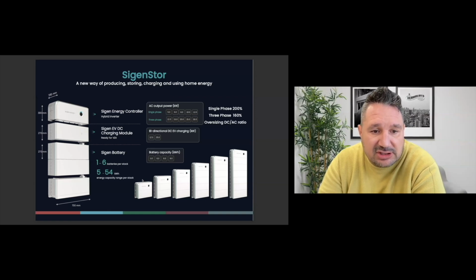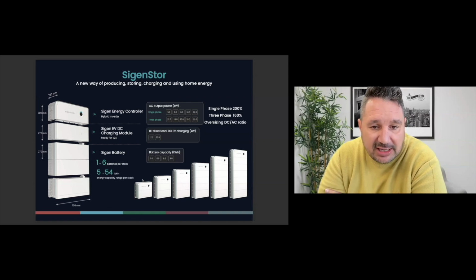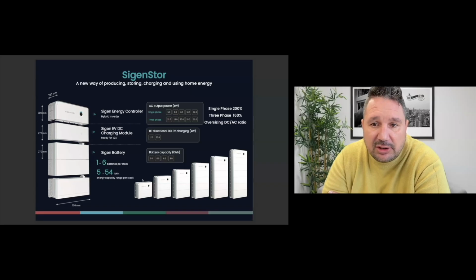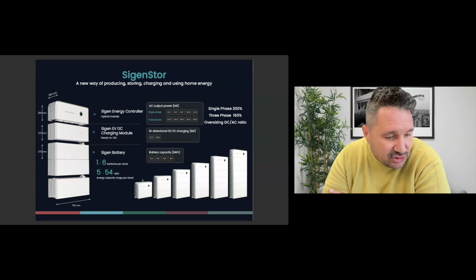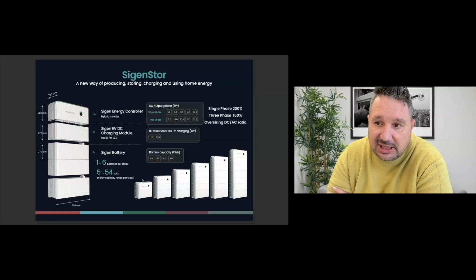When it comes to the batteries, you can stack up to 6 modules per stack, and the batteries come in a 5, 6, 8, and 9 kilowatt hour model. These can also be mixed and matched, old and new, different sizes, as well as the inverters can also be paralleled in any configuration you want. So if you need 40 kilowatts of inverter power, you can use a 15 and a 25, or 2x20s, or a 12 and a 30. This does not matter. You can mix and match them as you like to build the perfect scalable system that you need.